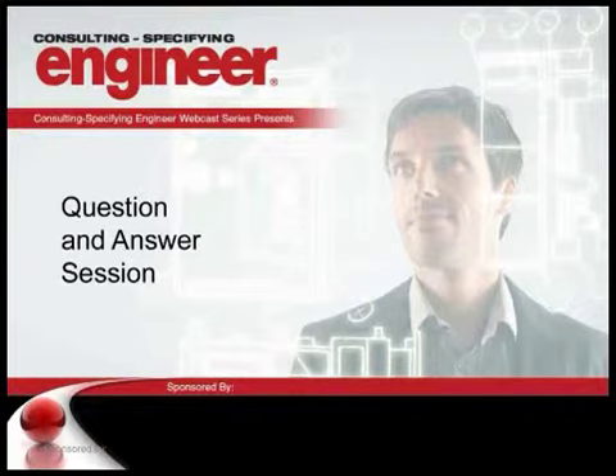Hey, Jim, by the way, there was a comment from Mark Rogers from Minneapolis saying that the generator curves that you were using do not seem typical of what SKM Power Tools typically shows for generators. Do you have any comment about that? The curves that I presented in the presentation were actually made using SKM. SKM doesn't have a good way to model a PMG, so you actually have to manipulate the curve to make sure that it looks like your unit is going to perform with the PMG.